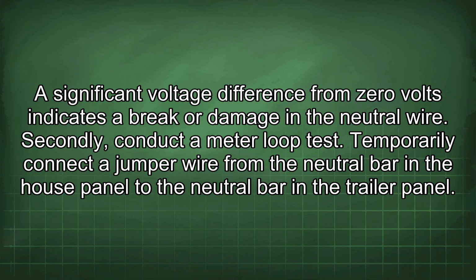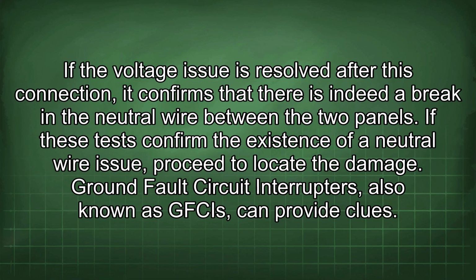Secondly, conduct a meter loop test. Temporarily connect a jumper wire from the neutral bar in the house panel to the neutral bar in the trailer panel. If the voltage issue is resolved after this connection, it confirms that there is indeed a break in the neutral wire between the two panels. If these tests confirm the existence of a neutral wire issue, proceed to locate the damage.